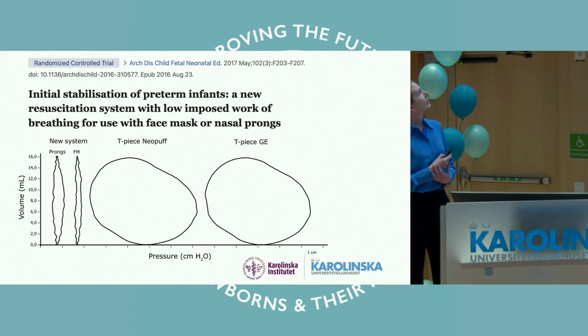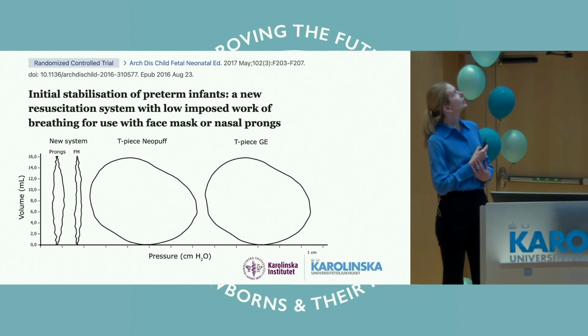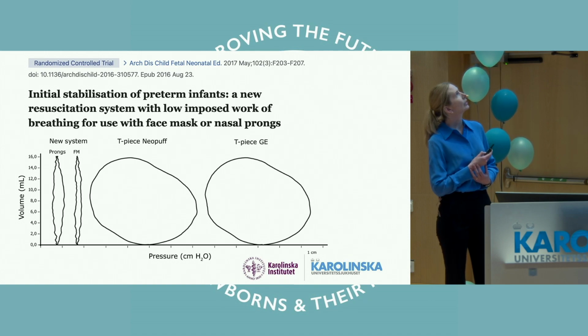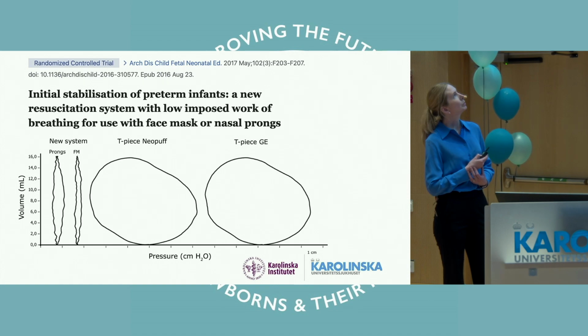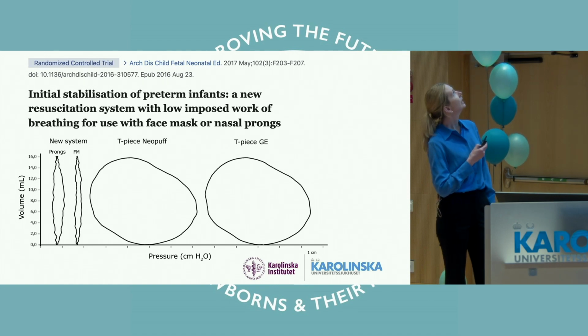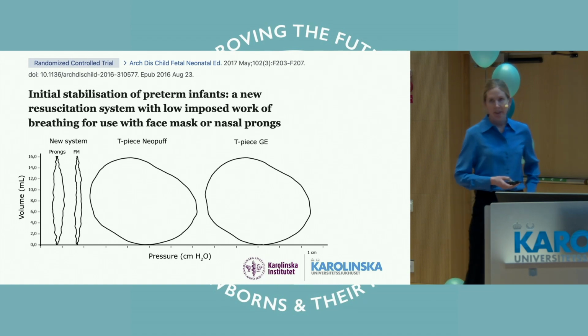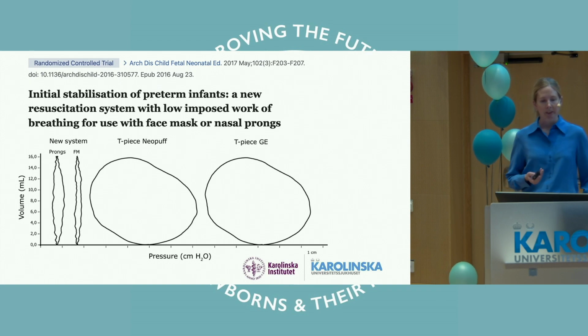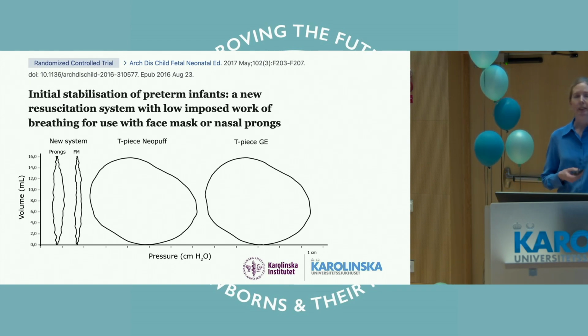We can see that on inspiration, the pressure drops, and on expiration, the pressure rises. And this creates the pressure volume loop that has a larger surface area for the T-pieces compared to the new system. And this surface area represents the work of breathing that is needed to breathe through the system.